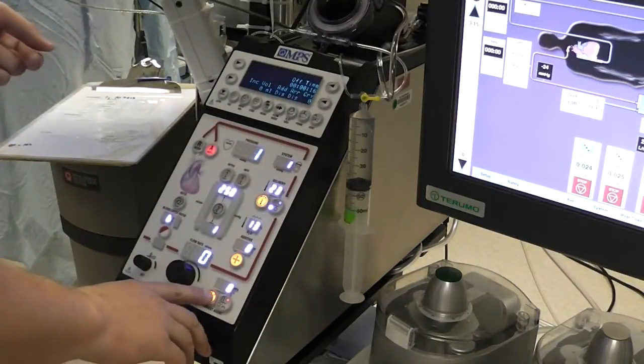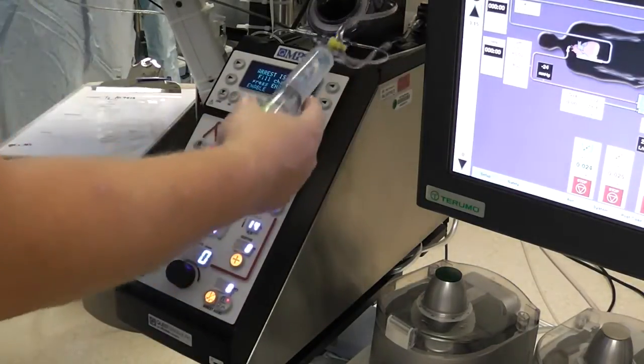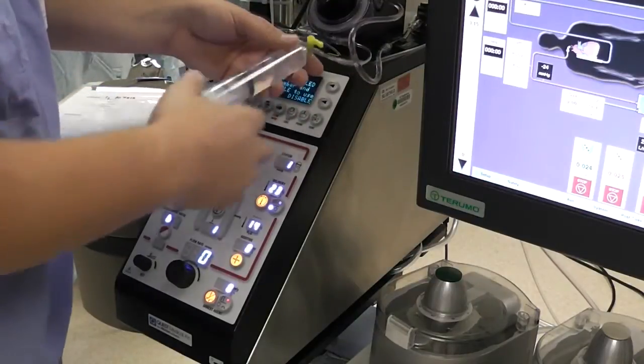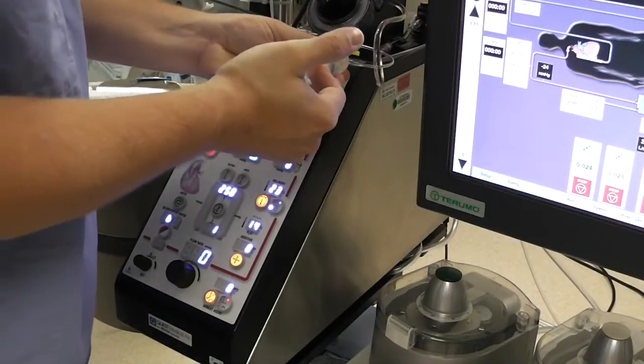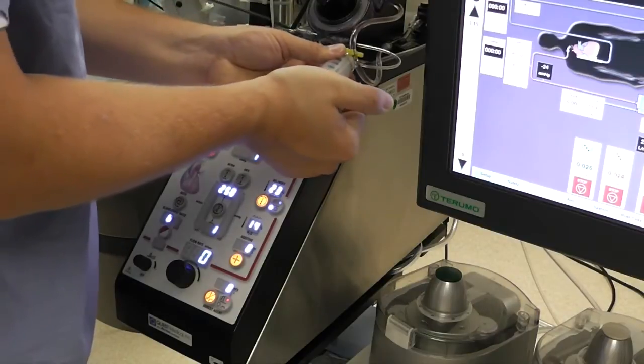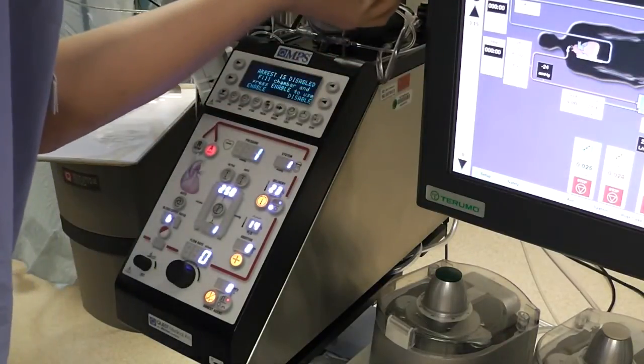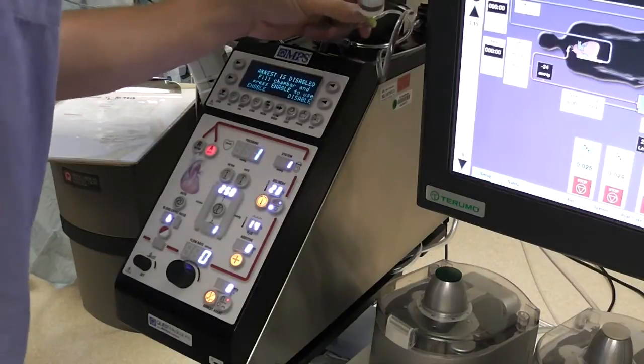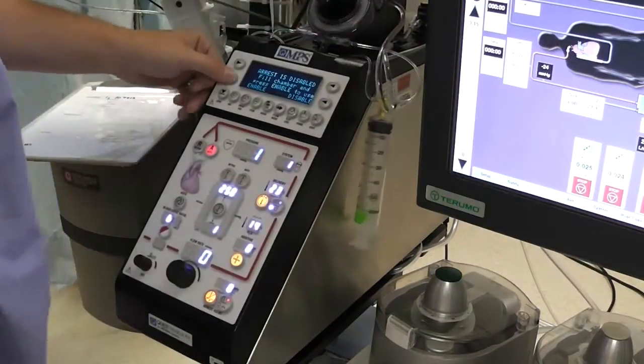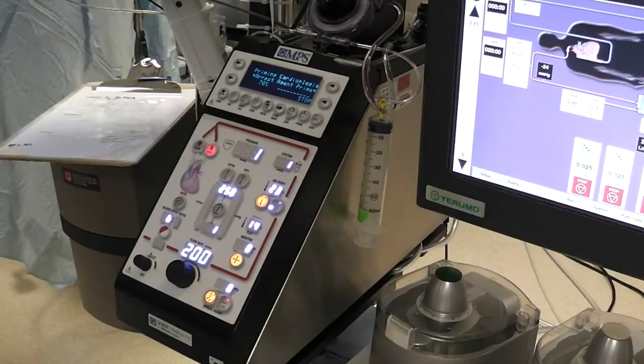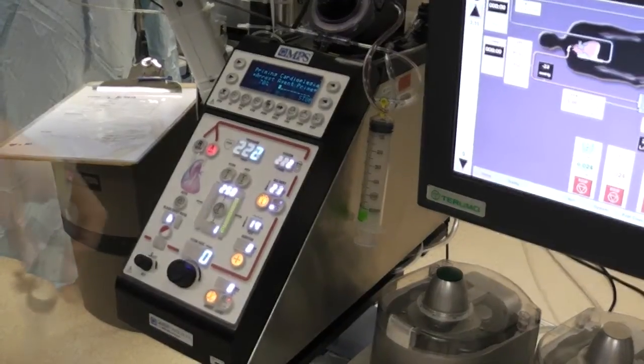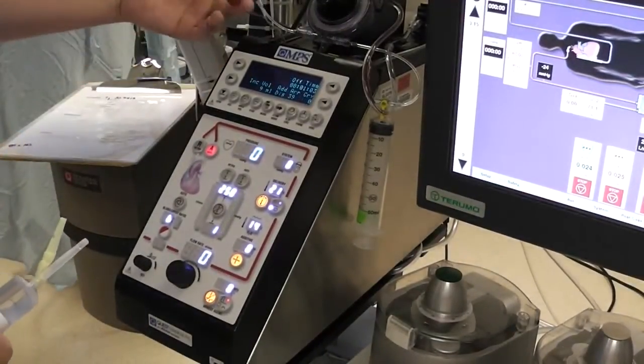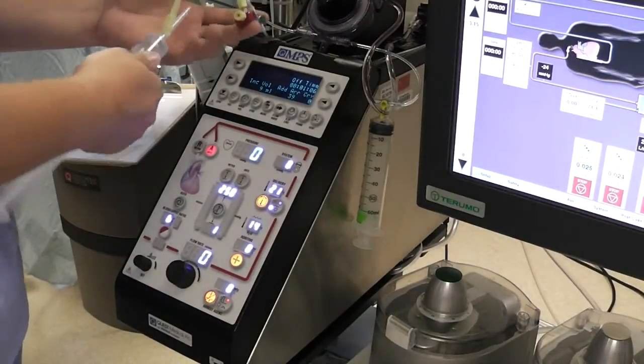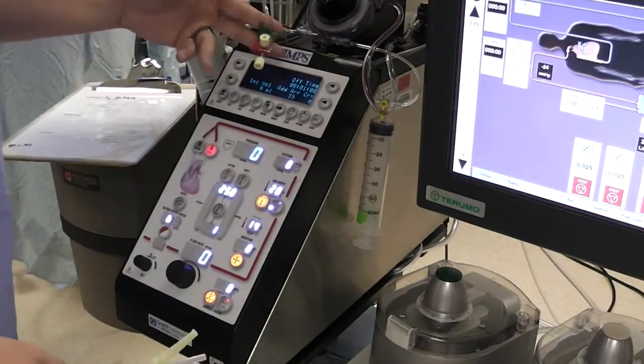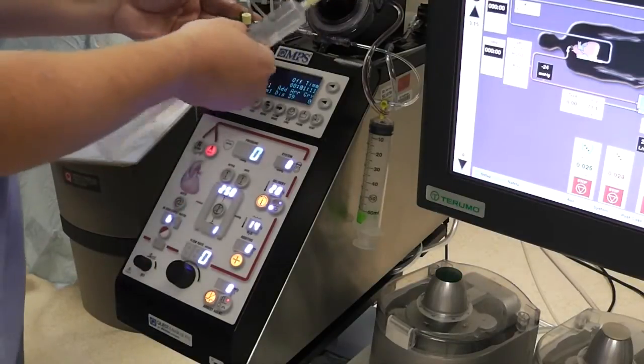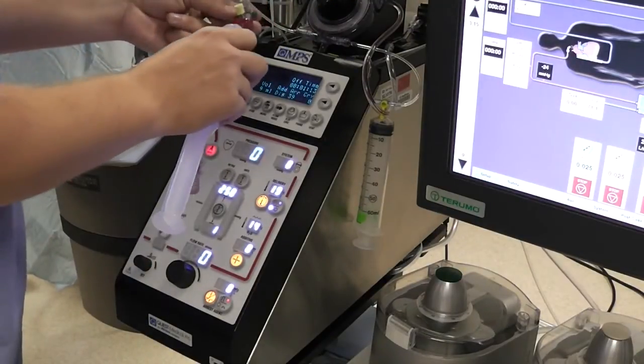We're going to hit arrest agent. Open up this yellow stopcock here. Push this all the way in. Pull back on the syringe to remove any air. Close that yellow stopcock back up and hit enable. It'll do its thing here for a minute while it primes that. Okay, now we're going to do a similar thing with our substrate and mag sulfate. So we're going to attach those to this. There's a secondary stopcock on here. We're going to put those on.